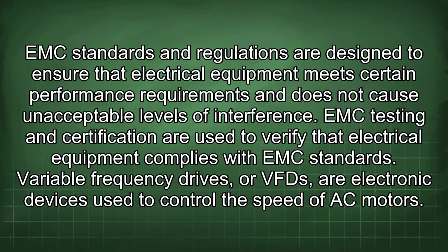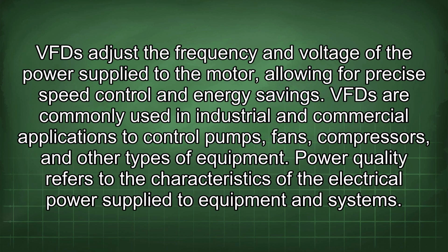Variable frequency drives, or VFDs, are electronic devices used to control the speed of AC motors. A VFD adjusts the frequency and voltage of the power supplied to the motor, allowing for precise speed control and energy savings. VFDs are commonly used in industrial and commercial applications to control pumps, fans, compressors, and other types of equipment.